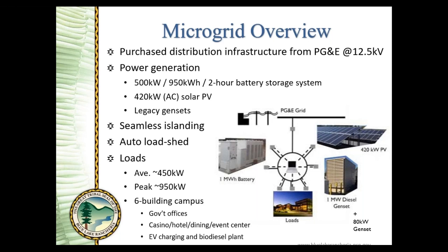In terms of power generation, we have solar PV and battery storage. Right now we have about 420 kilowatts AC of solar, and we're looking to double that in the next year and a half. We have basically a megawatt hour of battery storage, 500 kilowatts of power there. Just to give you a sense of perspective, that battery system alone can power our whole campus on New Year's Eve, when everything's going, for 2 full hours. That doesn't seem like a lot of time, but it's actually a really powerful system, and the footprint is super small, probably a 10-foot wide by 20-foot long pad is all it takes to get that battery in there.